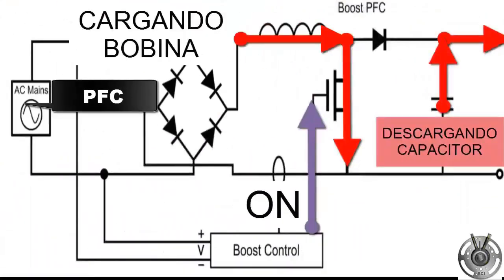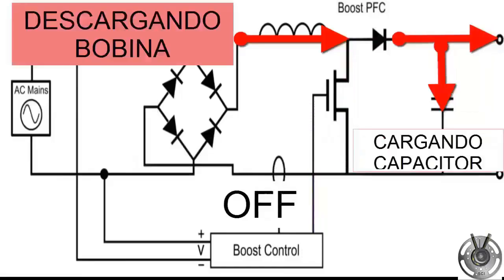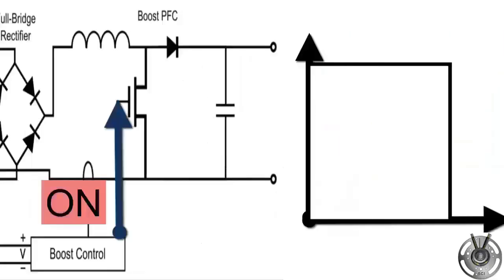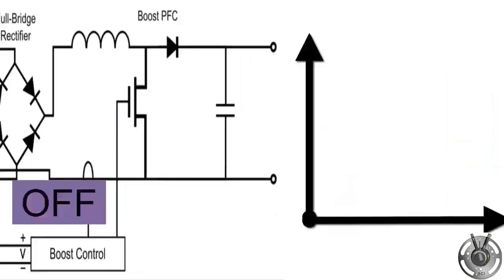The reactor stores energy in its magnetic field when the current flows through it, that is, when the IGBT transistor is on. The electronic controller, through control strategies, determines when the energy accumulated in the reactor is sufficient to replace the energy that is entering. At that moment, the controller deactivates the IGBT and suspends the current supply.